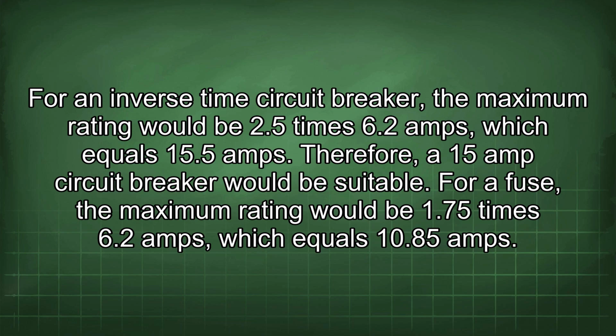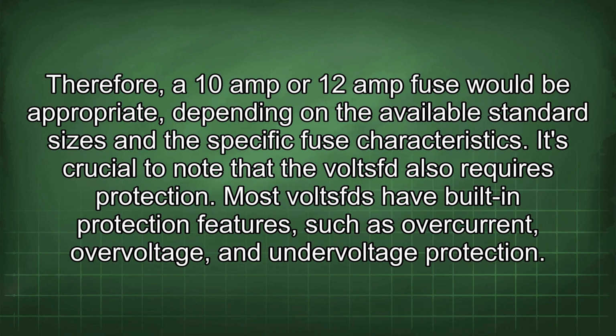For a fuse, the maximum rating would be 1.75 times 6.2 amps, which equals 10.85 amps. Therefore, a 10 amp or 12 amp fuse would be appropriate, depending on the available standard sizes and the specific fuse characteristics. It's crucial to note that the VFD also requires protection. Most VFDs have built-in protection features such as overcurrent, overvoltage, and undervoltage protection.